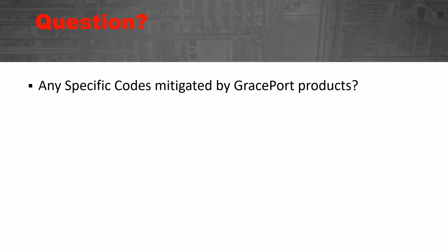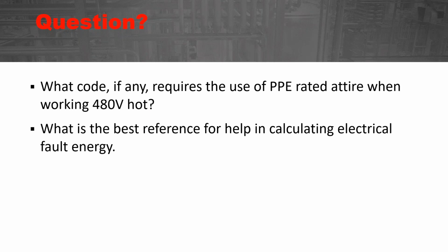Okay. So next one, I think this is for you, Jay. What code, if any, requires the use of PPE rated attire when working 480 volts hot? And what is the best reference for help in calculating electrical fault energy? Yeah, so to answer the first question, that would be NFPA 70E and also OSHA 1910, the regulations. Those are the two sources that we'd look into as far as PPE for 480 volt hot. As far as the second question, what's the best reference for calculating? That would be IEEE 1584, 2018 edition.